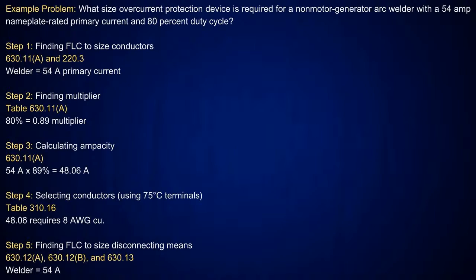It's 54 amps and it has an 80% duty cycle. Okay. So the first portion, in step 1, get your amperage. That's what we always do. So we know it's 54 amps. Now I'm finding a percentage again. So I'm going to come over and look for a non-motor generator type. I'm going to come down and look at 80%, come across. It's going to tell me that the multiplier is 89%.